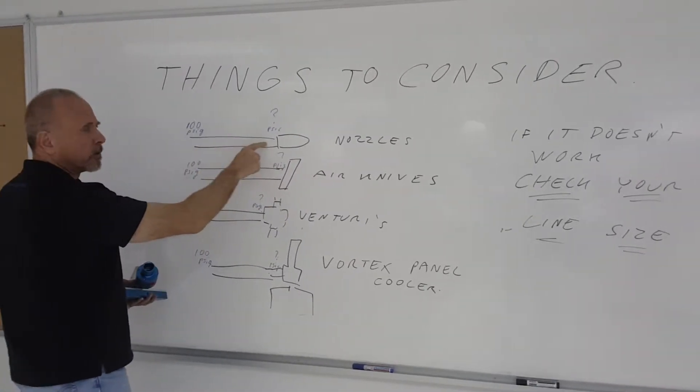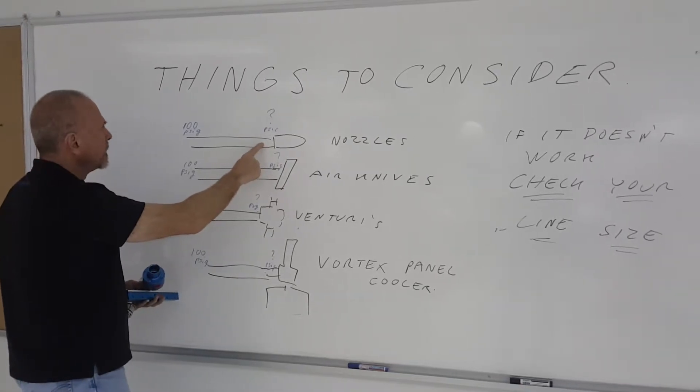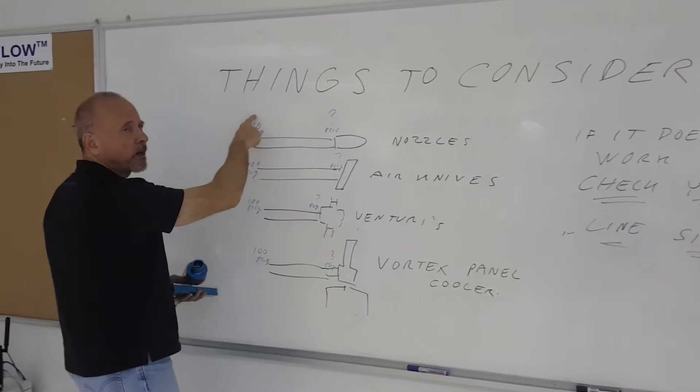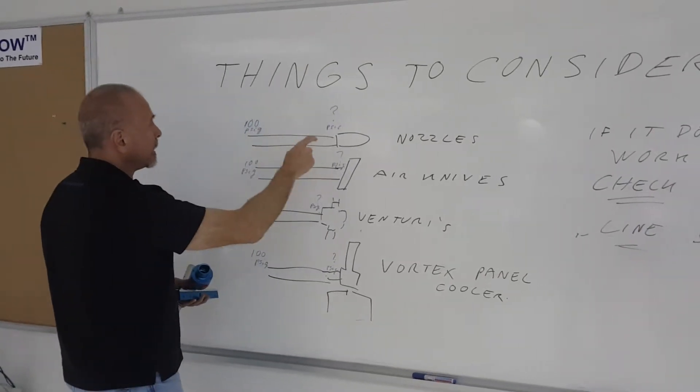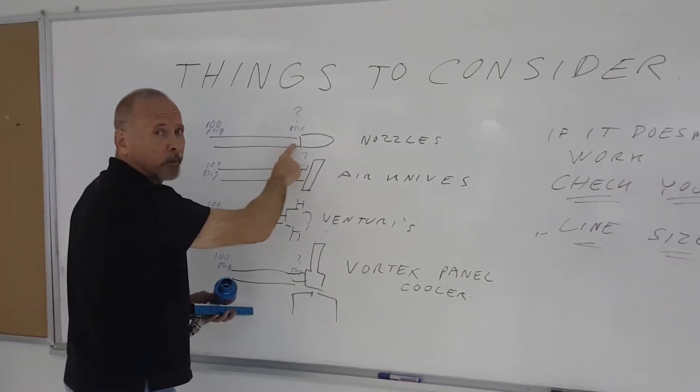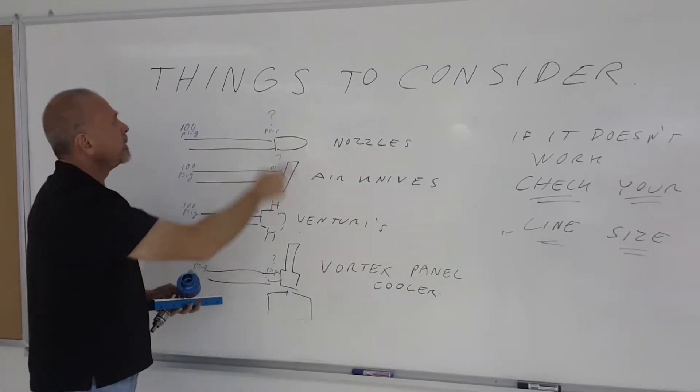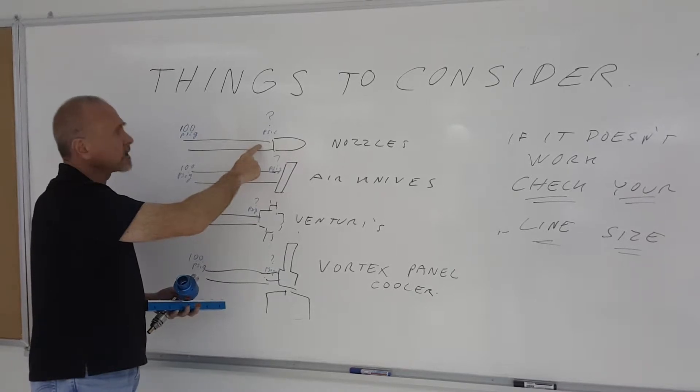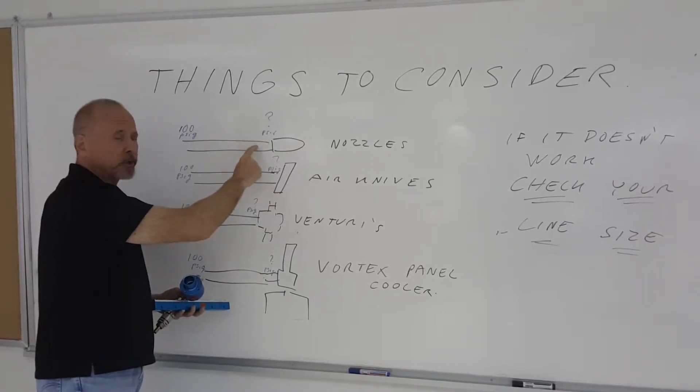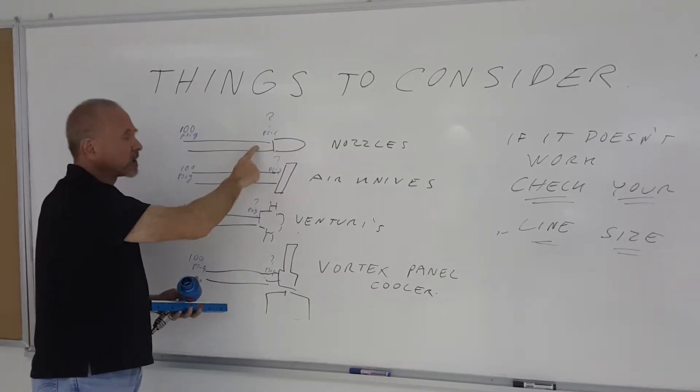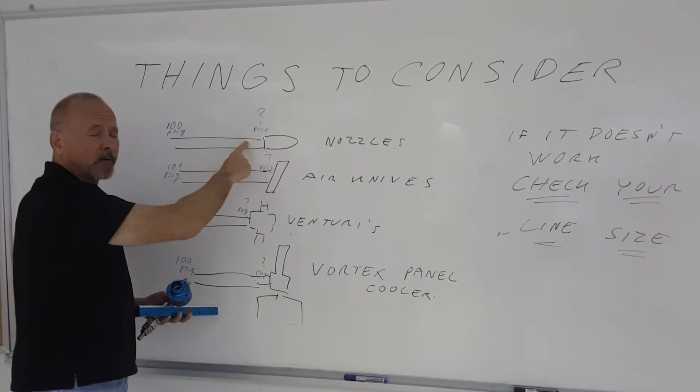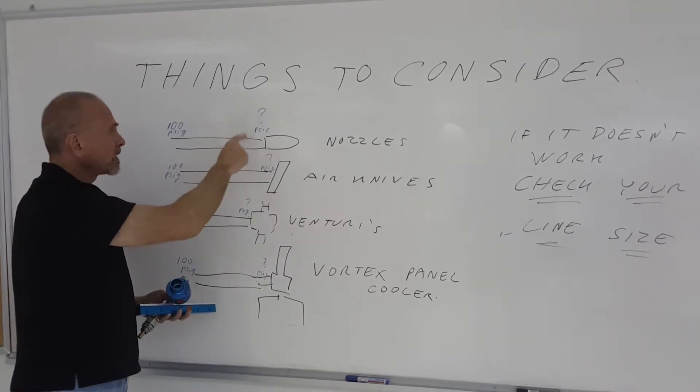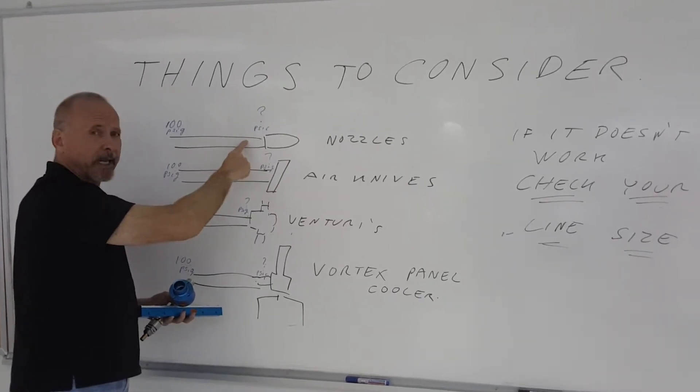So they may be reading at a pressure gauge 100 pounds per square inch upstream, but it may not be that at the point of use. If you want to be sure, you put a pressure gauge a few inches upstream from that point of use and you measure the pressure while it's running, because while it's running, that's when the air is flowing. They'll give you a reading of the actual pressure at the point of use. If it's much less than what the specs say, then obviously you've got too high a pressure drop in the line.